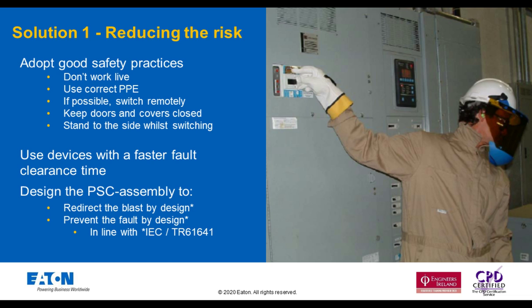Obviously, other good working practices are using the correct level of PPE. Arc flash studies can be carried out to ascertain the correct level of PPE required, and this is a service that Eaton will offer if anybody's interested. Along with not working live, remote switching is another possibility. That takes the person away from the electrical switchgear, and the opening and closing of circuit breakers can be done remotely outside the switch room.